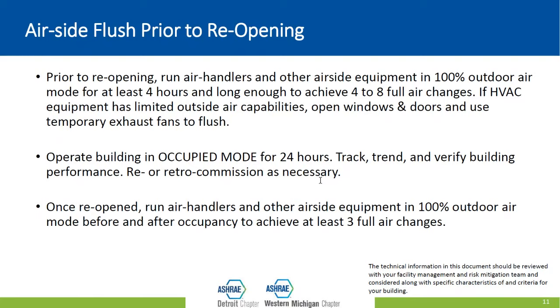And then finally, once you're actively using the building, you want to do a daily flush before and after occupancy. You want to try to achieve at least 3 full air changes. Or if you don't know whether or not you're getting the full air change, 2 hours before and after you occupy the building should be sufficient. And this is all to help ensure that used air that may be contaminated, that we've breathed in and coughed in, gets exhausted. And you want to have a good foundation of indoor air of acceptable quality to start off your next occupancy cycle.